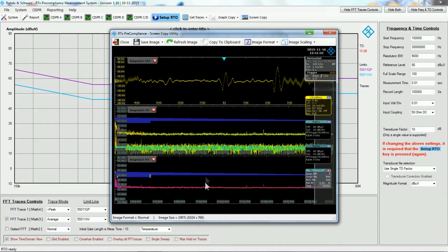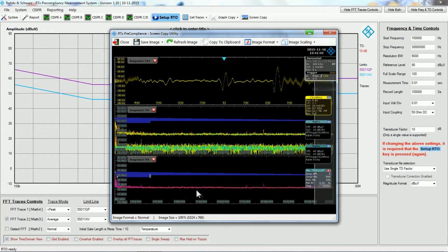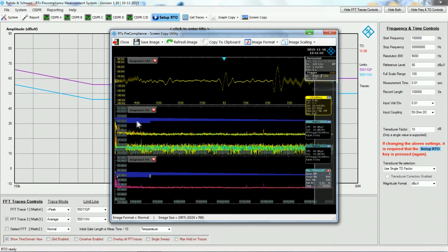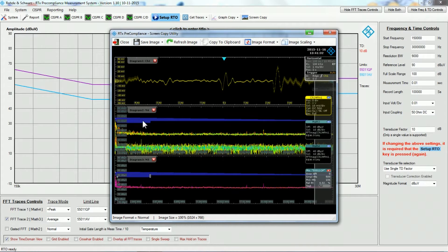And we have another one here running in average mode to get the average detector mode. The bars that we have up here is a mask that is being set up to emulate the typical limit lines that we also see on the screen.